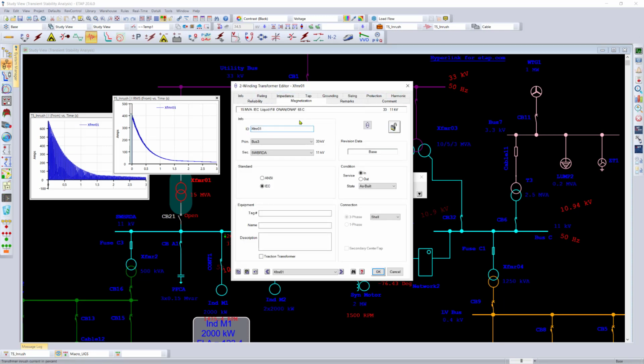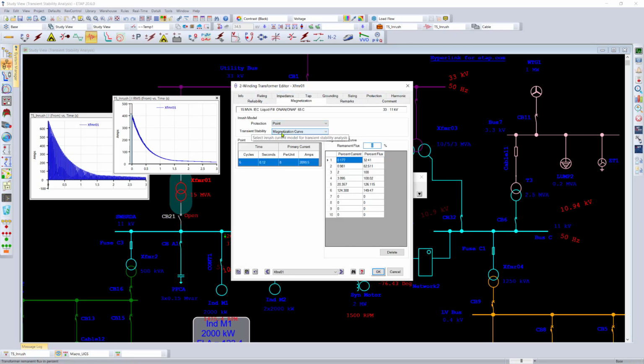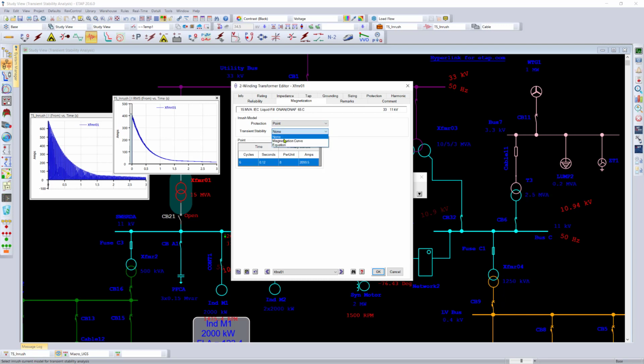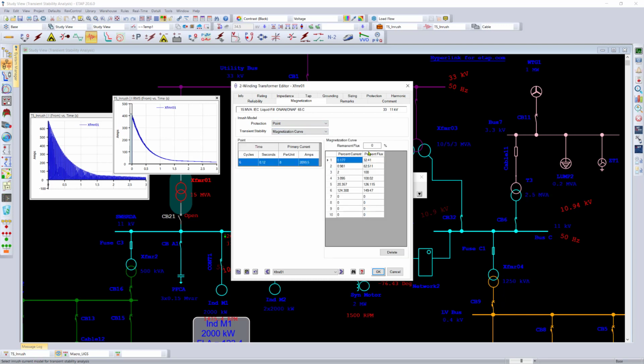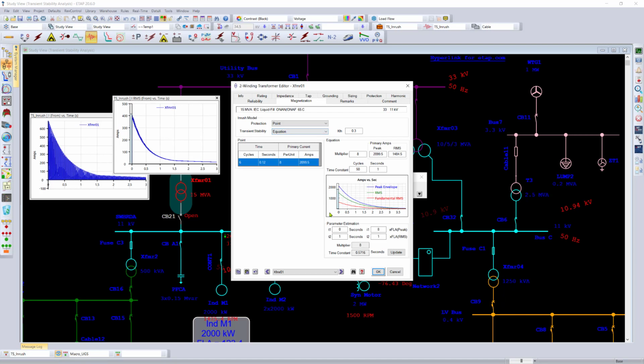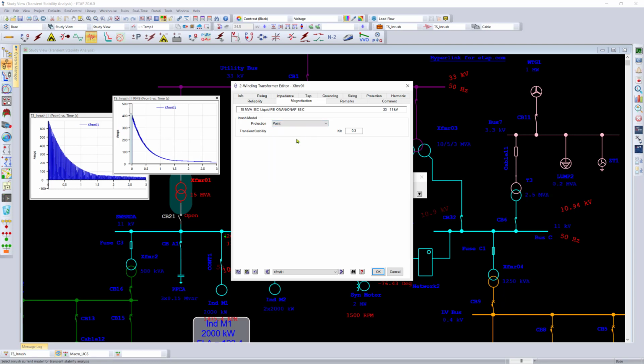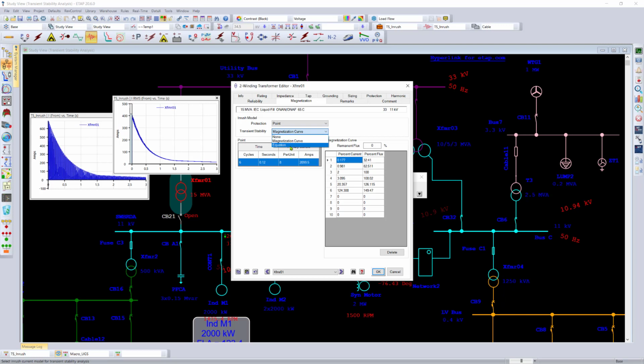The ETAP 20.6 magnetization page also includes the ability to use a magnetization curve for the inrush, which is based on percent current and percent flux, and you can also put in the remnant flux as well. But in 20.6, you can also use an equation-based approach where the peak current time can be plugged in by the user along with the peak FLA value, and you can also plug in the second time where the RMS current is considerably less compared to the peak value. And based on these parameters, the program can estimate what the inrush curve would look like instead of you typing in these magnetization values manually.